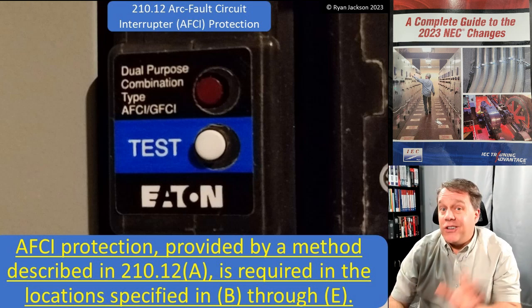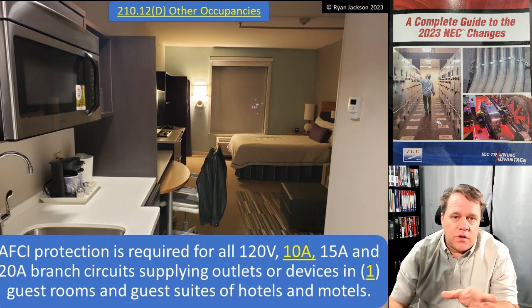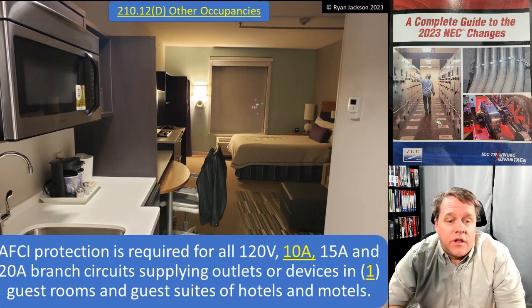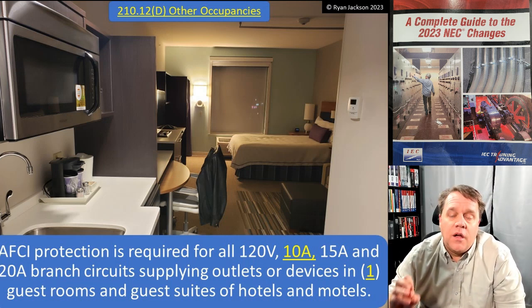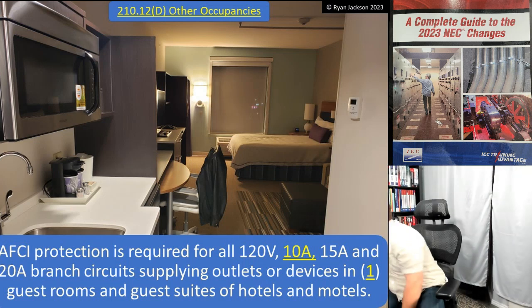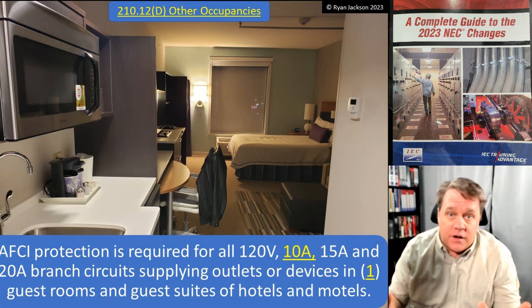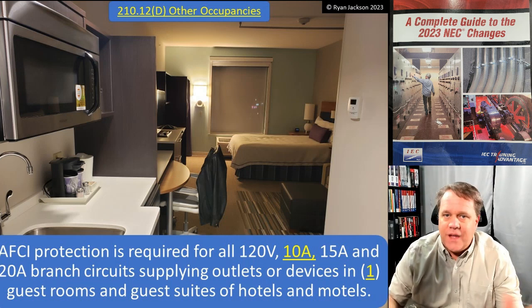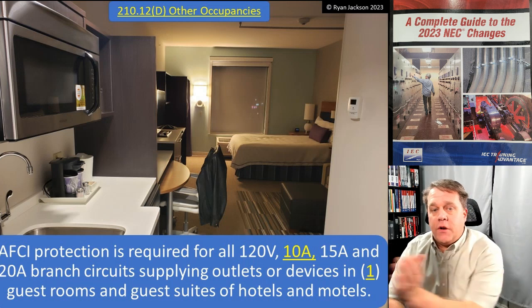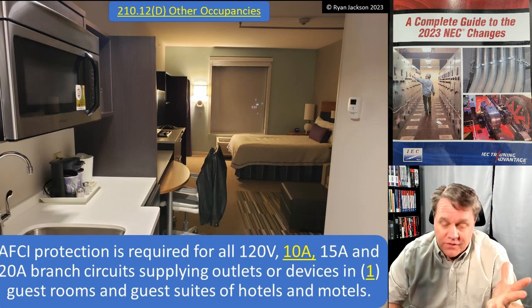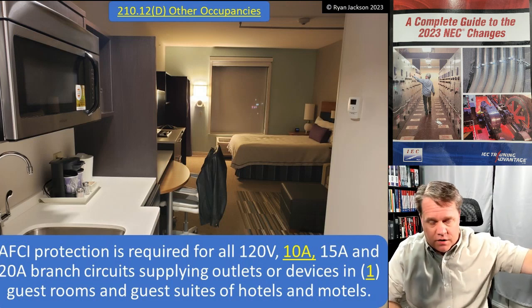Not a lot of changes here. They added 10-amp circuits, so 210.12(d) now requires AFCI protection for all 120-volt, 10-amp, 15-amp, and 20-amp branch circuits supplying outlets or devices. But let's set aside the 10-amp thing — they're not making a 10-amp AFCI. Nobody's putting in 10-amp circuits right now. If some things happen in 2026 you might see 10-amp branch circuits, but for right now, just forget that.